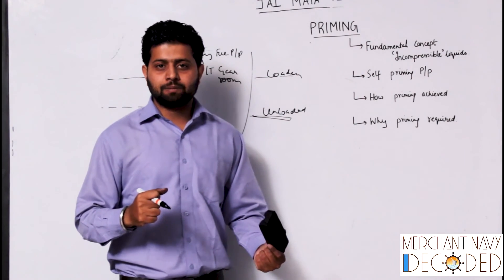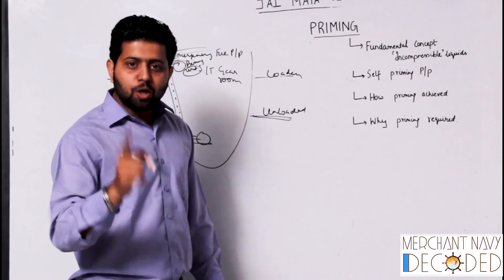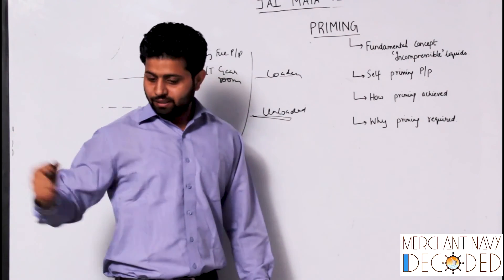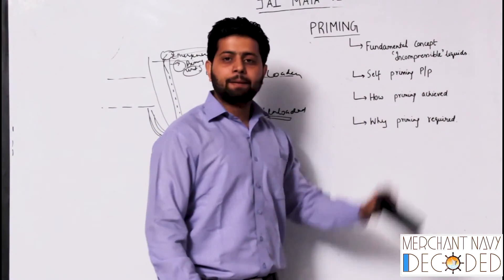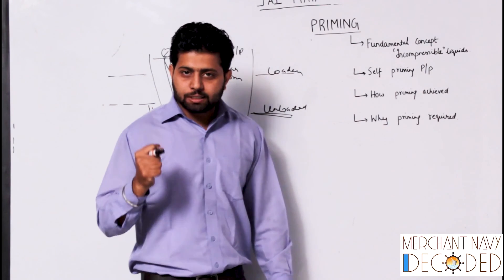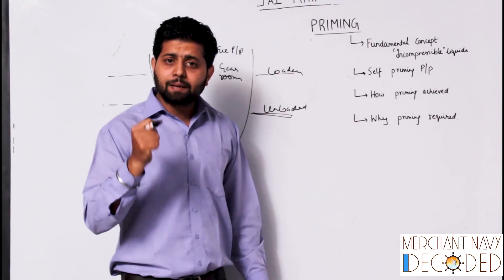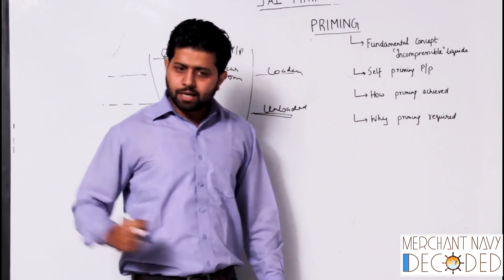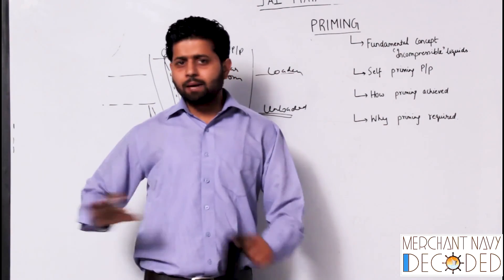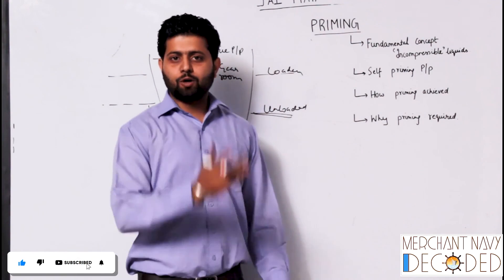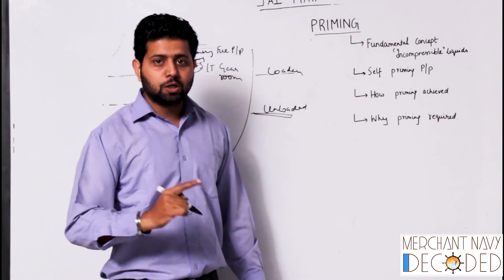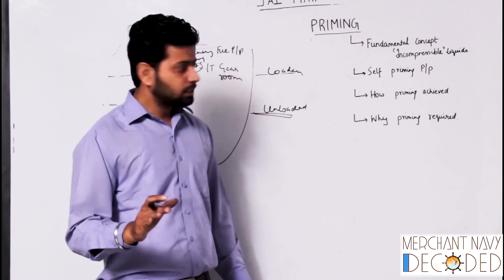What about positive displacement pumps? They are not bothered about air at all. Let air come in, let oil come in, let anything come in — they will pump it. So even if air enters, it gets pumped out. That is why positive displacement pumps — gear pumps, screw pumps — are called self-priming pumps. They do not need a separate priming unit. But when it comes to centrifugal pumps, we must be very careful that air does not enter the system, or we will damage the pump.